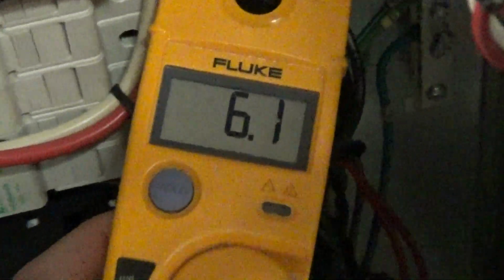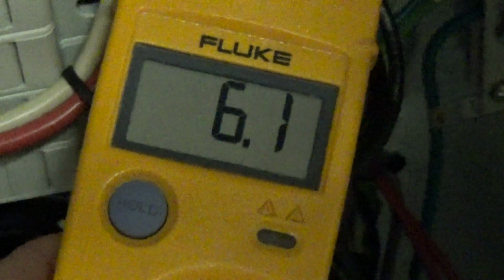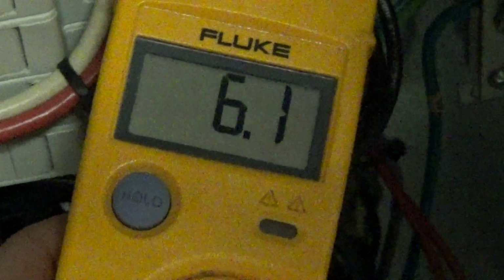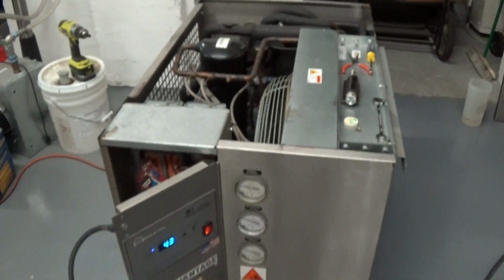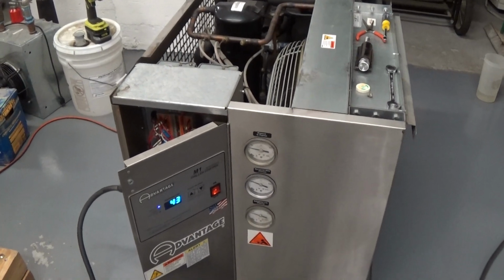So always be careful when you're in a control cabinet. Right now, oh, I'm sorry, I'm on the wrong one. Yeah, that makes more sense. So, right now in this environment, compressor on, pump on, fan on, drawing about 6.1 amps. If it was 90 degrees in here, 95, I'd say it's probably going to draw about 10 or 20% more than that, just working a little bit harder.